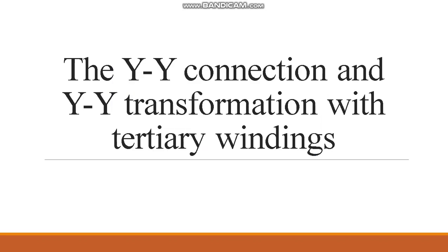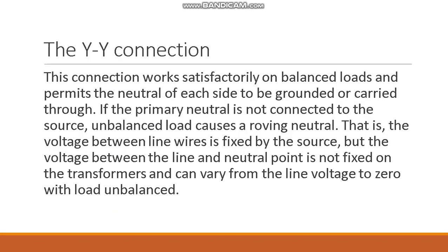The Y-Y connection works satisfactorily on balanced loads and permits the neutral of each side to be grounded or carried through. If the primary neutral is not connected to the source, unbalanced load causes a roving neutral — that is, the voltage between the line wires is fixed by the source, but the voltage between the line and neutral point is not fixed on the transformers and can vary from line voltage to zero with load unbalanced.